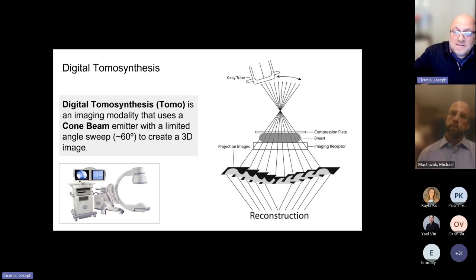It's the same process, the same imaging, somewhat the same algorithms. It's just that by convention a cone beam CT is generally 180 degrees or more of a sweep, whereas digital tomo is a more mitigated sweep, somewhere between 60 and 100 degrees. As a result you don't get as much data with digital tomo, and you have to be more clever in how you collect your image.